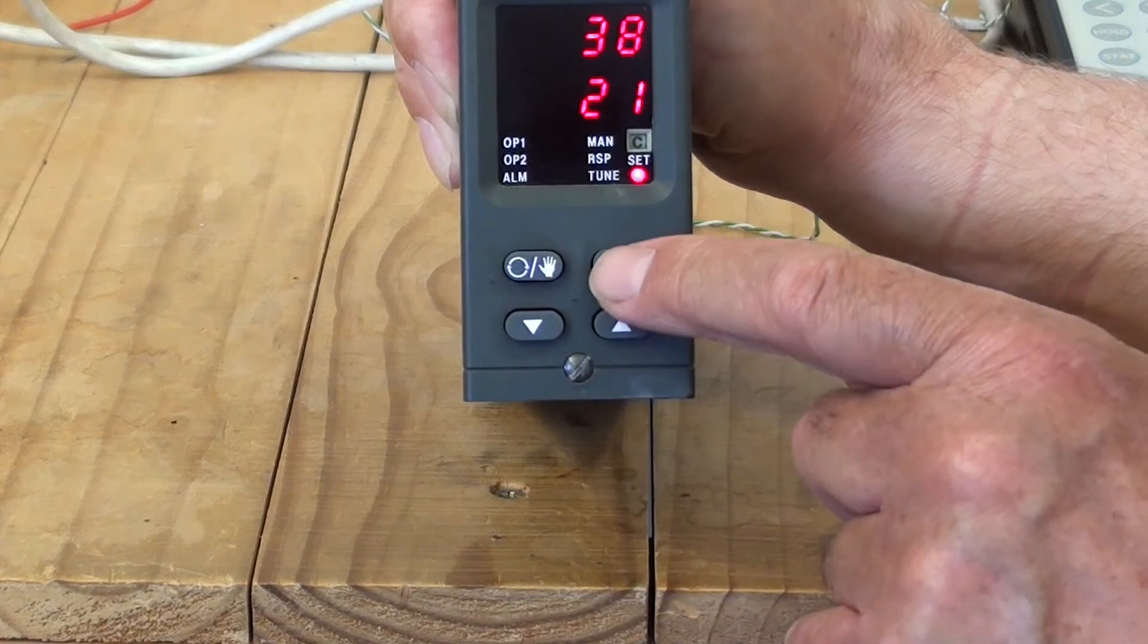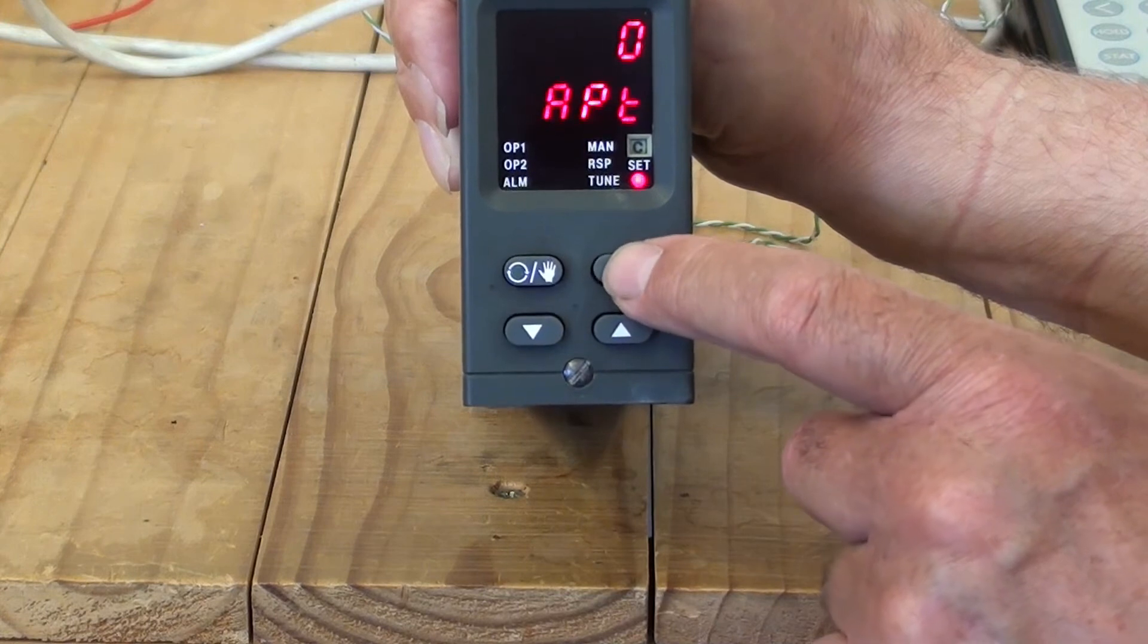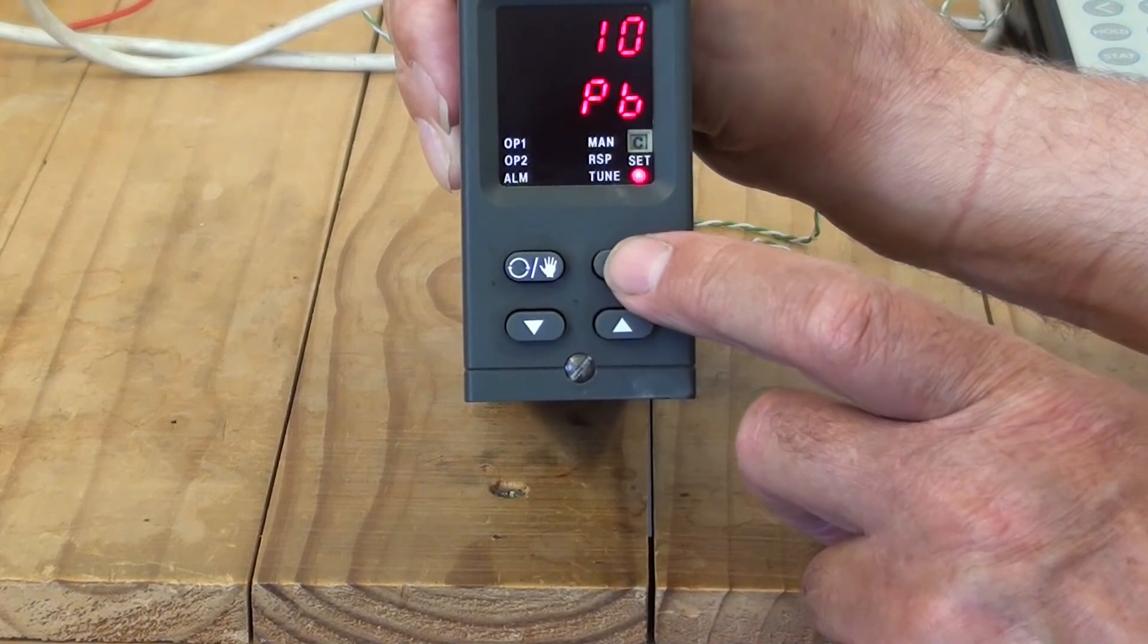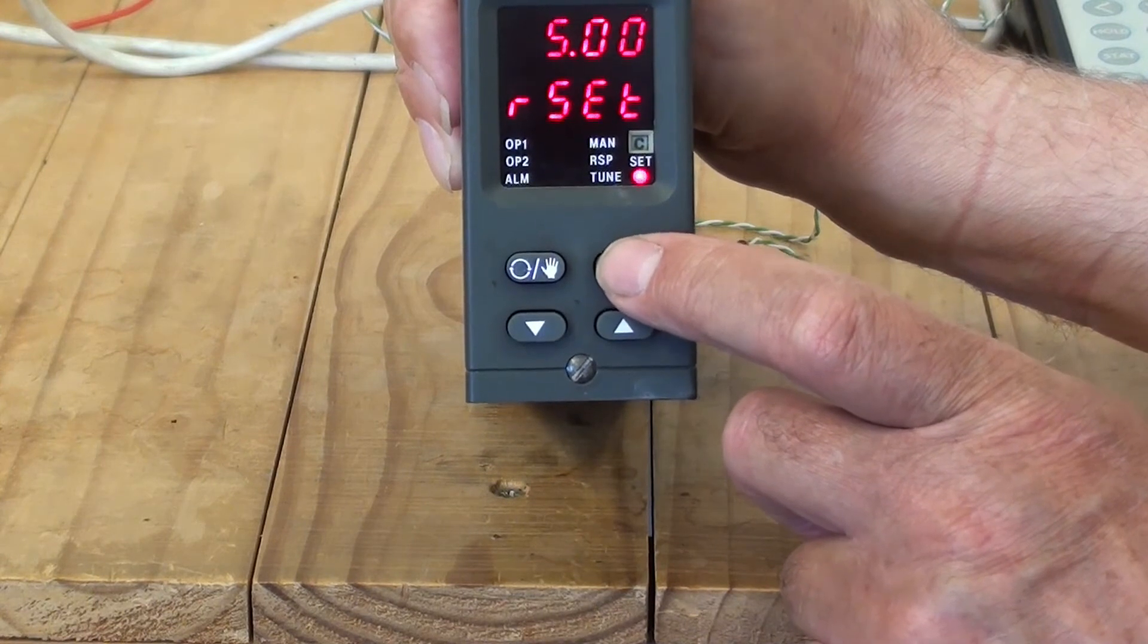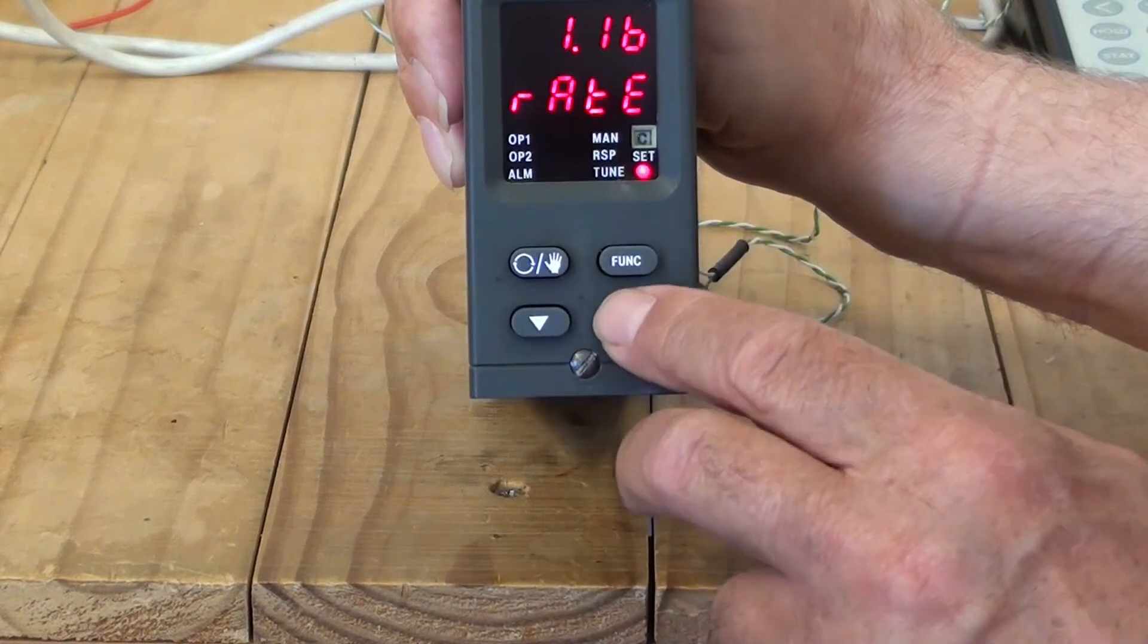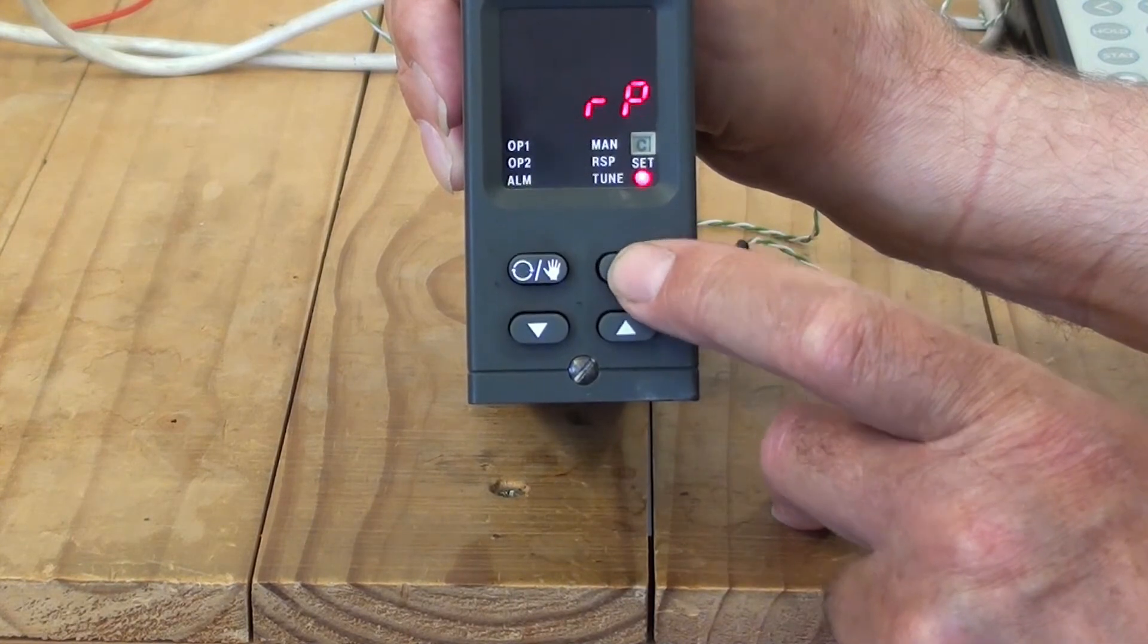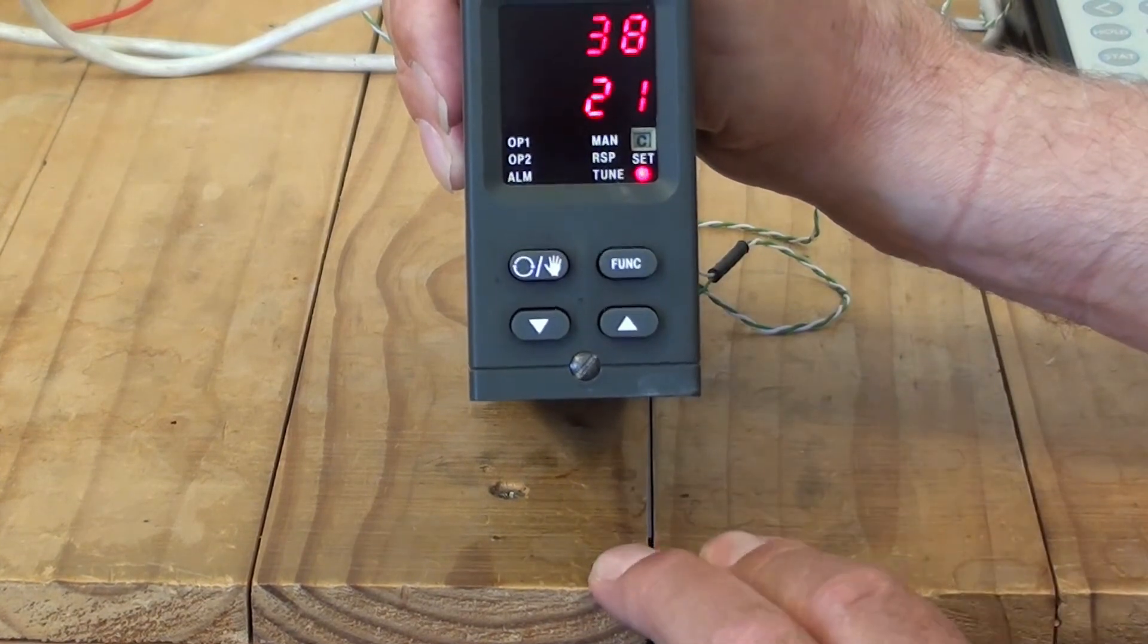If you press the function key you can then scroll through that menu. So here for example, now I'm in that menu. This shows me the output power. Here's the PID terms - proportional band, the reset (the integral time), the rate (the derivative time). You can adjust these of course by just using the up and down arrows. Setpoint limits, the high limit, the low limit, the outputs, cycle time, and exit.